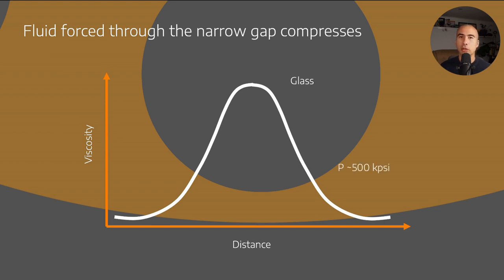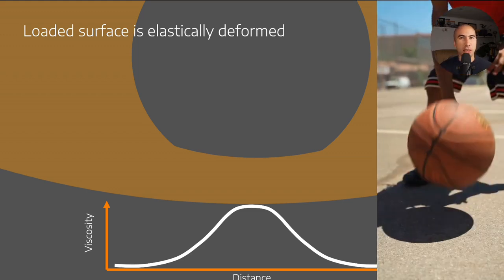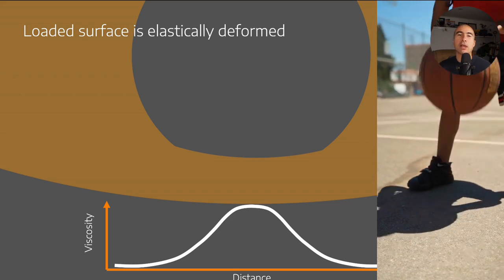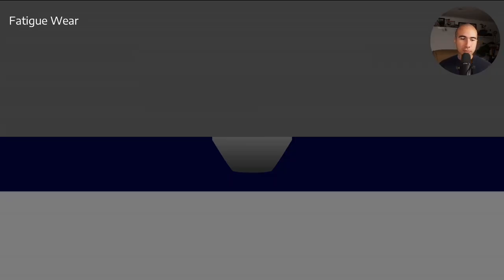The pressures are so high that they actually elastically deform the surface. If you could pause and look under a microscope, the rolling elements deform when they go through the load zone, like a basketball deforming when it bounces, then restored on the other side.